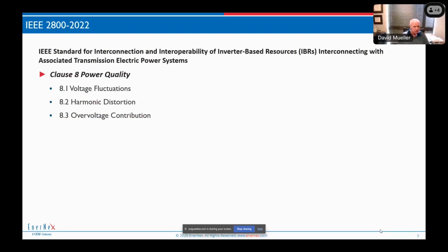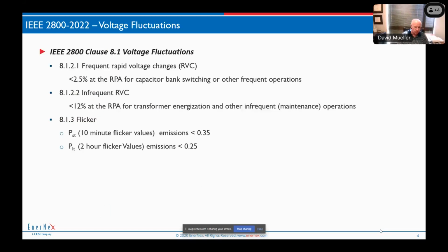So 2800, adopted 2022 now, so it's been out for a few years. The standard for interconnecting and interoperability of IBRs on the transmission system. Clause 8 was power quality. There are three parts to that clause, as I mentioned before: voltage fluctuation, harmonics, and overvoltage. So let's go through and look at those.